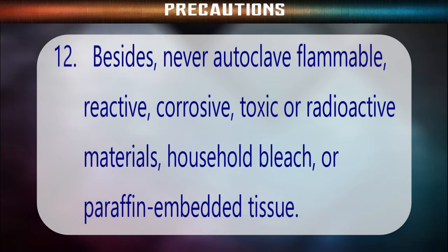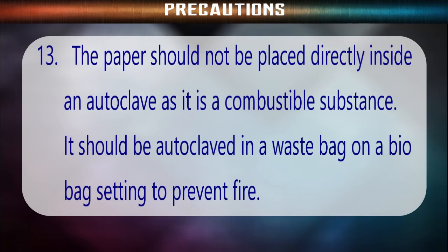Besides, never autoclave flammable, reactive, corrosive, toxic, or radioactive materials, household bleach, or paraffin embedded tissues. Paper should not be placed directly inside an autoclave as it is a combustible substance. It should be autoclaved in a waste bag on a bio bag setting to prevent fire.